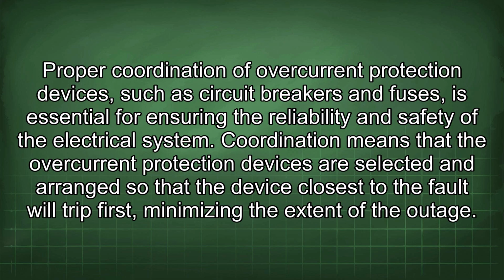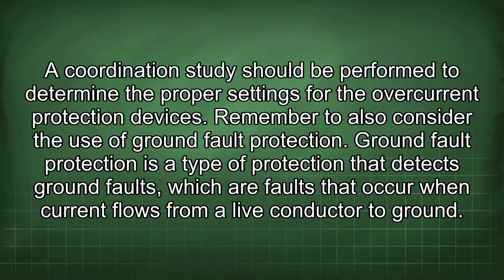Proper coordination of overcurrent protection devices, such as circuit breakers and fuses, is essential for ensuring the reliability and safety of the electrical system. Coordination means that the overcurrent protection devices are selected and arranged so that the device closest to the fault will trip first, minimizing the extent of the outage. A coordination study should be performed to determine the proper settings for the overcurrent protection devices. Remember to also consider the use of ground fault protection.